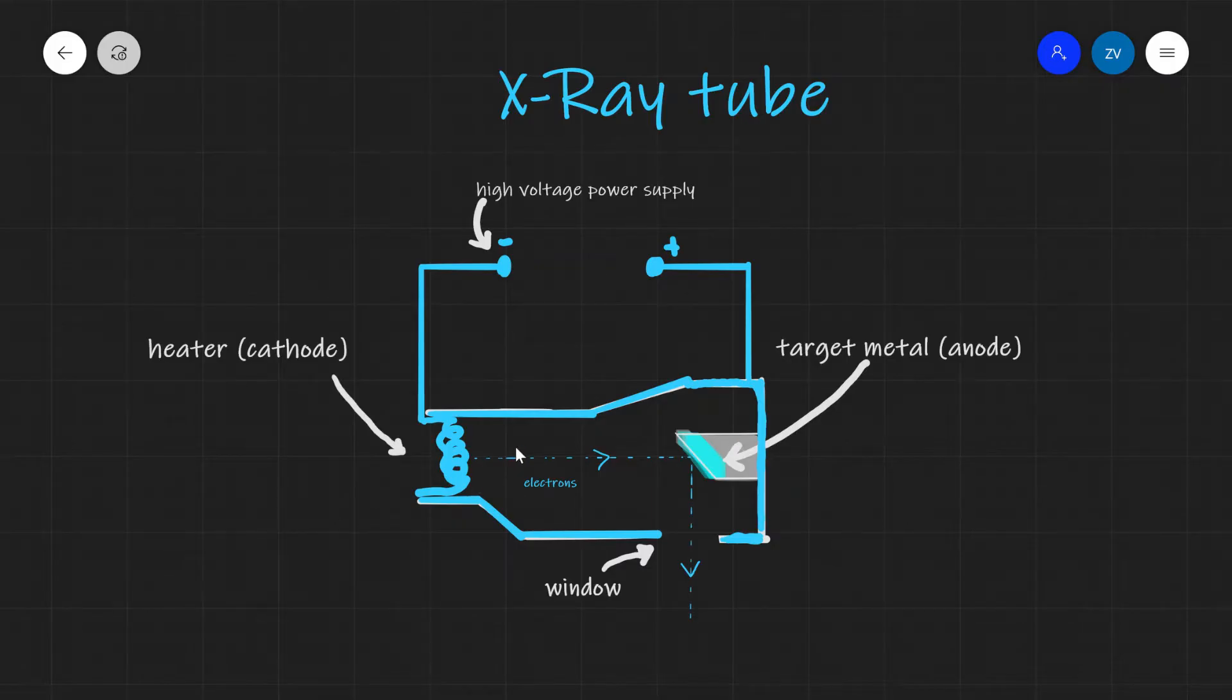Once the electrons are decelerated, they lose a lot of energy and only 1% of their kinetic energy is converted to x-rays. The x-rays will be emerging out of this window. And this beam over here is actually your x-ray beam.